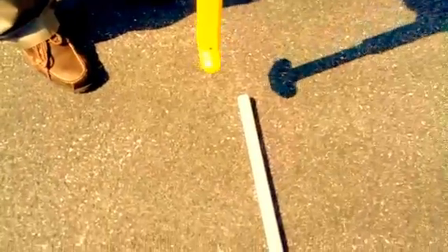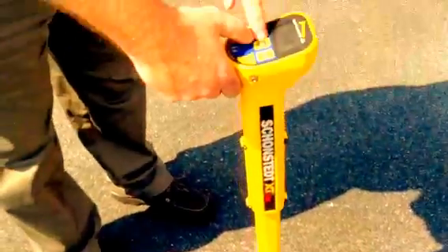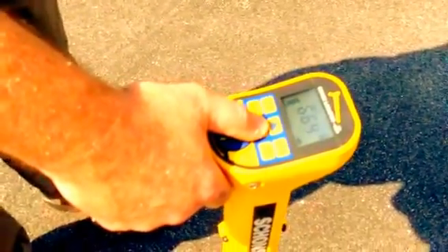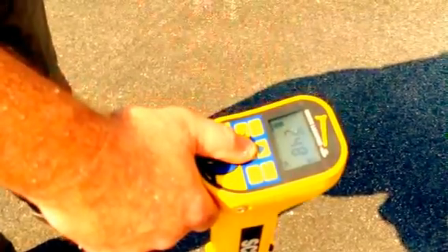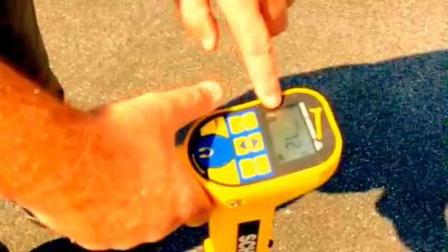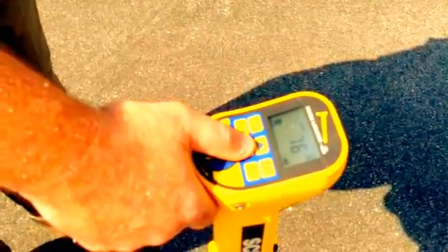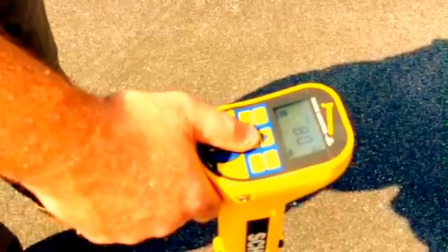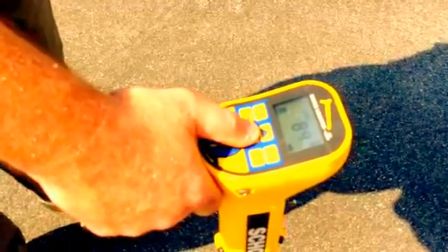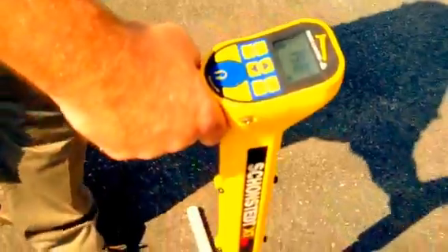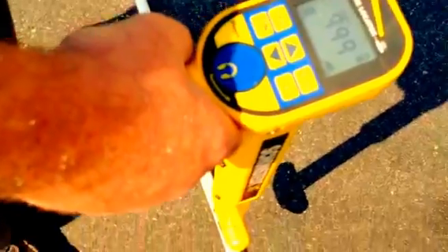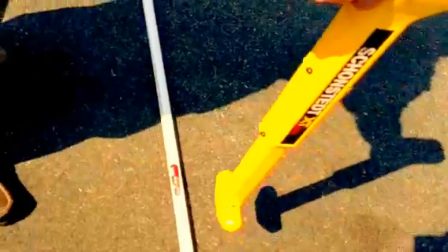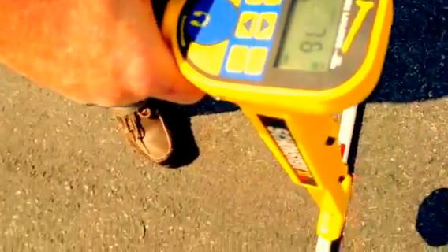At this point, to get precision, you will adjust your sensitivity with your up and down arrow buttons. When you do this, the signal strength relationship will give you a bar graph. The lower you hit the down arrow button, the less sensitivity you're using. Now, this will help me pinpoint the sonde's position within the pipe more accurately by keeping my sensitivity low. Notice that the peak is going up again when I am directly over and in line with the beacon. I'm getting even more precision by lowering the sensitivity even further.